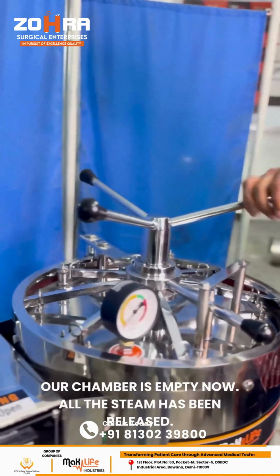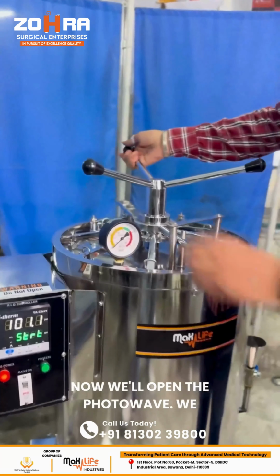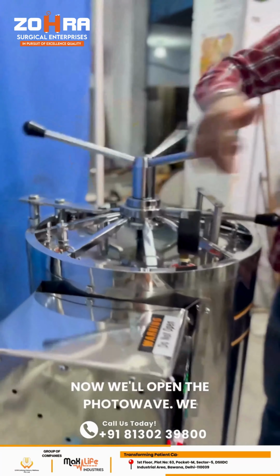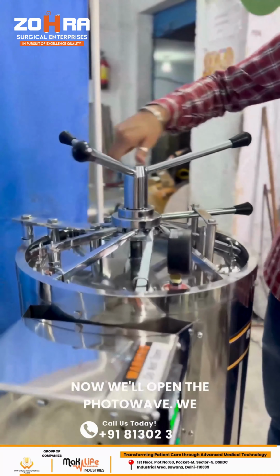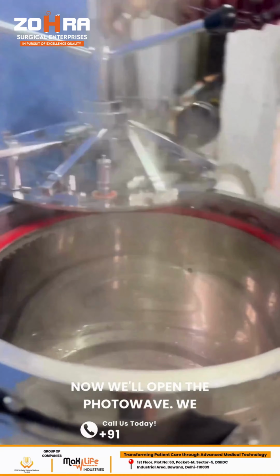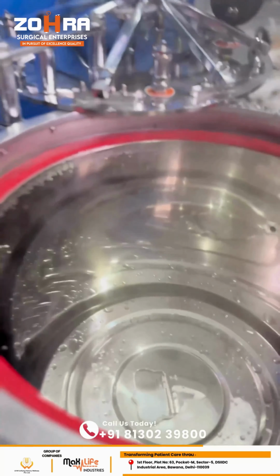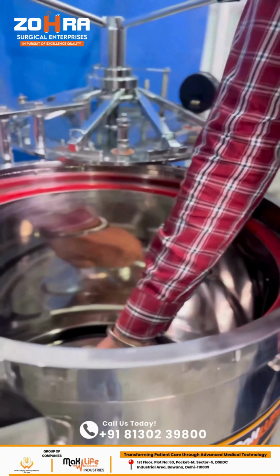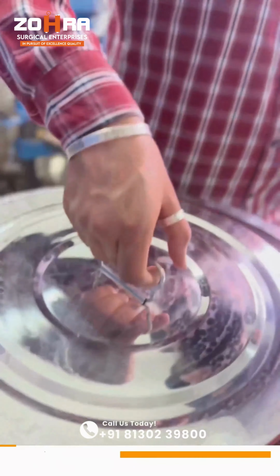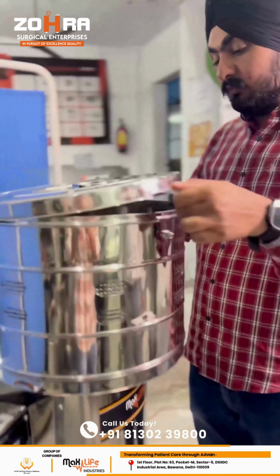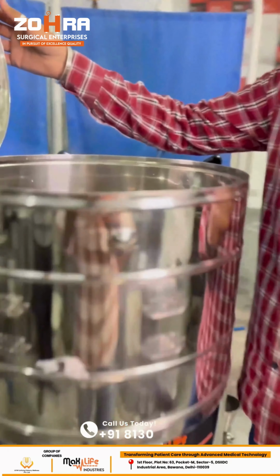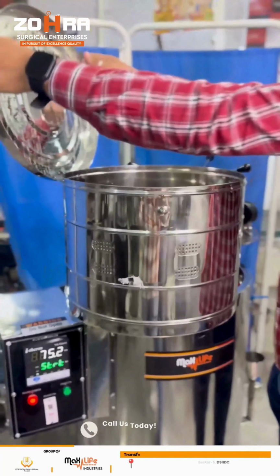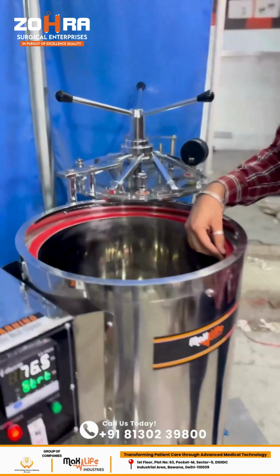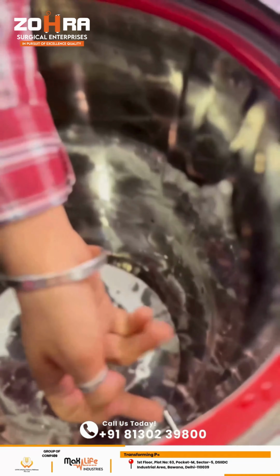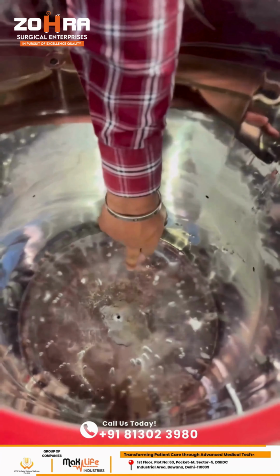So our chamber is empty now, all the steam has been released. Now we'll open the autoclave. Plate to this side. You can check it's maximum dry. Now we show you inside your plate. So this is our silicone basket. This is a temperature sensor, and this is a hole for extra water.